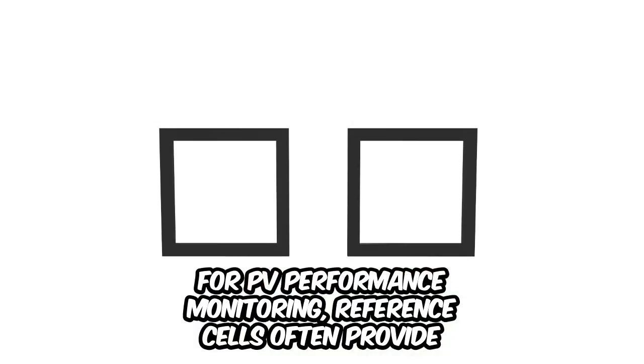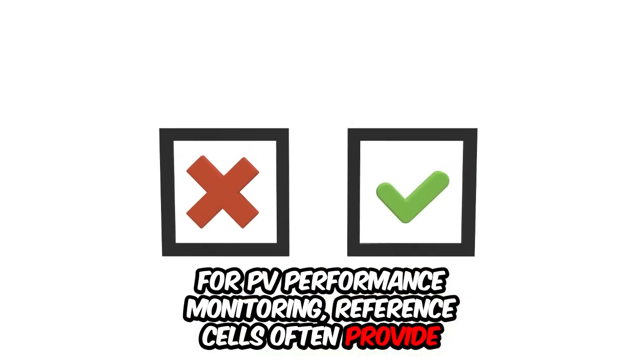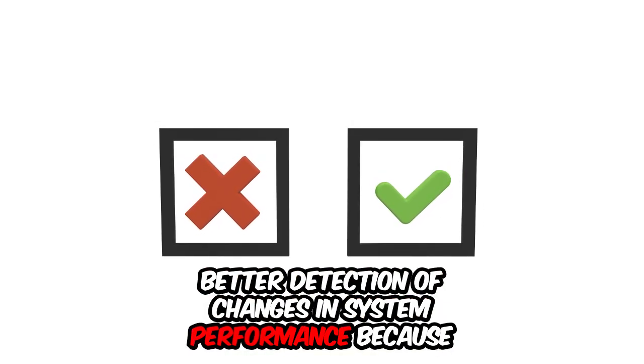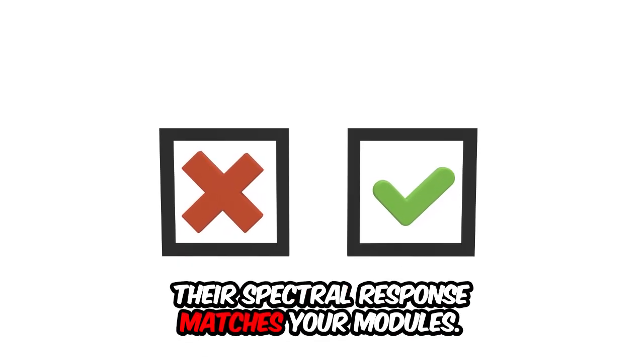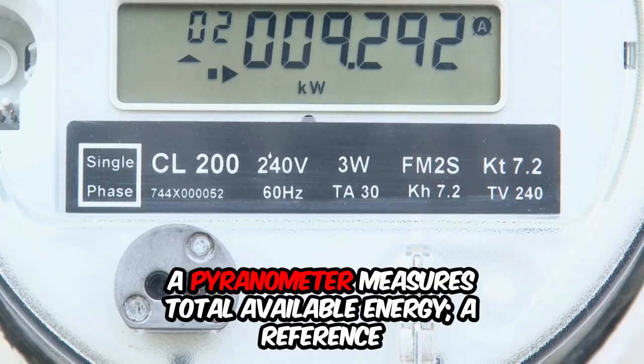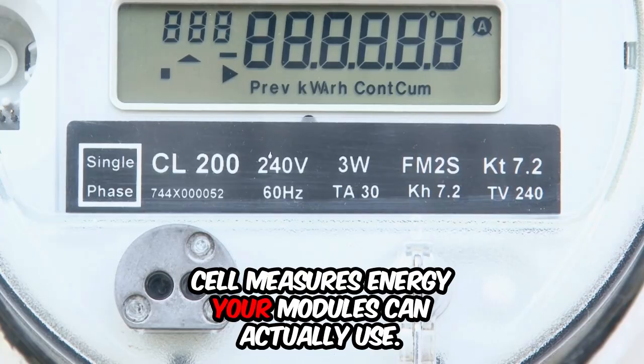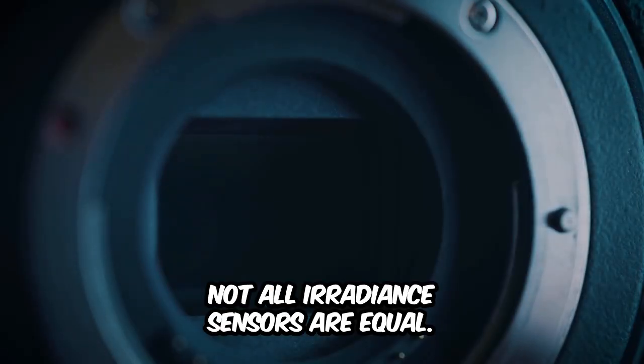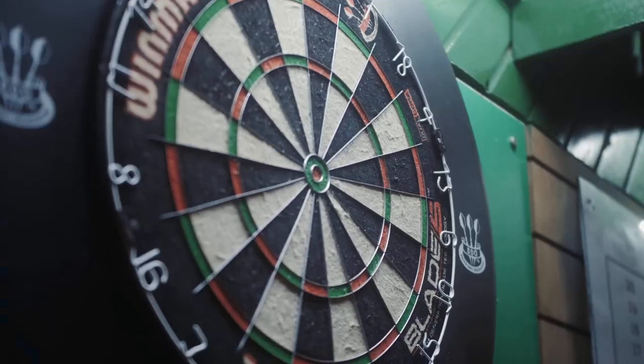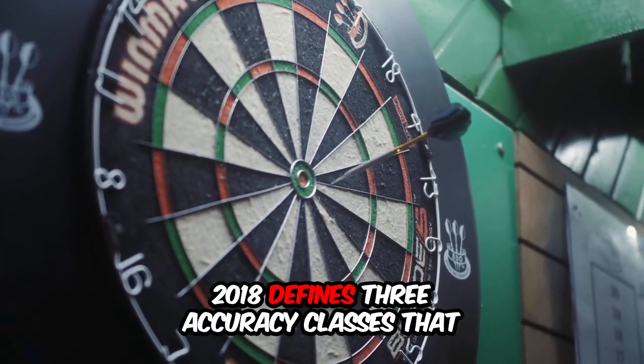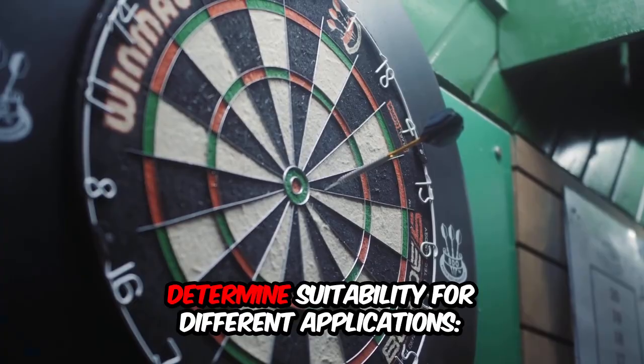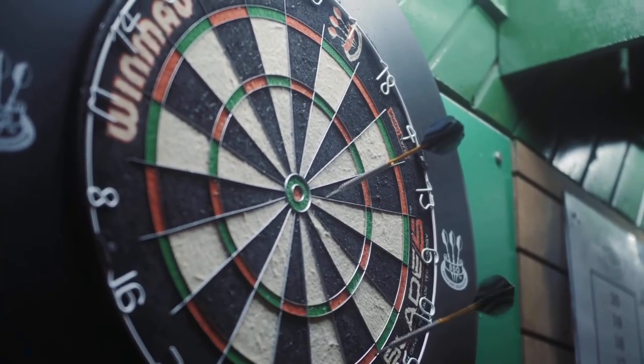For PV performance monitoring, reference cells often provide better detection of changes in system performance because their spectral response matches your modules. A pyranometer measures total available energy. A reference cell measures energy your modules can actually use. Not all irradiance sensors are equal. ISO 9060:2018 defines three accuracy classes that determine suitability for different applications.